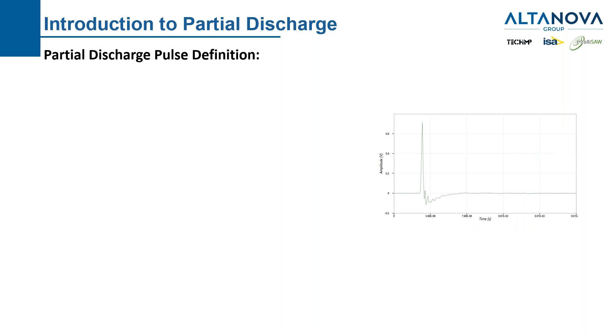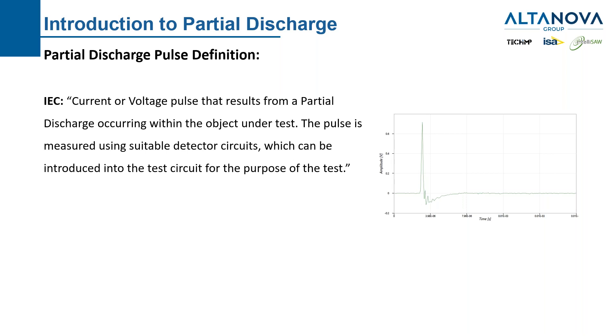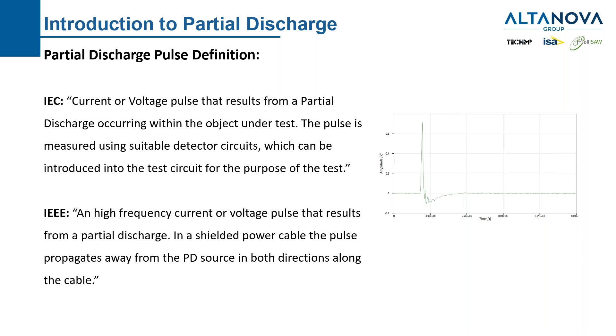Now let's define the partial discharge pulse. According to the IEC standard, a partial discharge pulse is a current or voltage pulse that results from a partial discharge occurring within the object under test. The pulse is measured using suitable detector circuits. According to IEEE, in a shielded power cable, the pulse propagates away from the discharge site in both directions along the cable. In short, a partial discharge pulse is a high frequency electrical pulse.